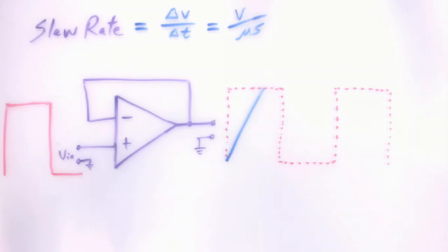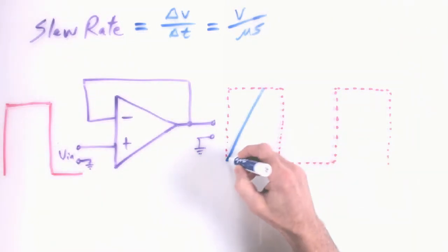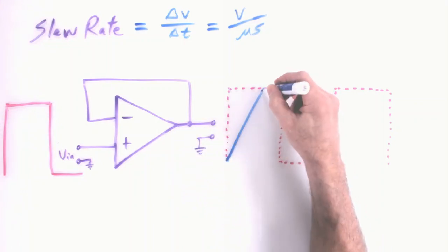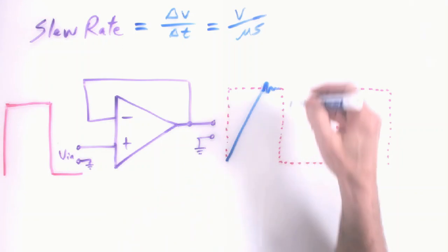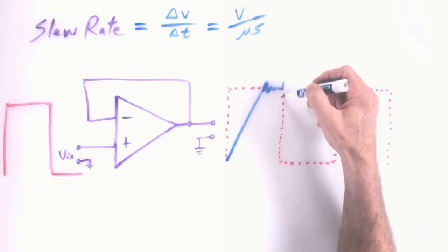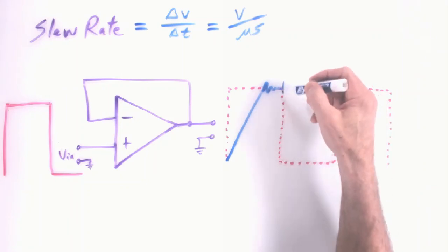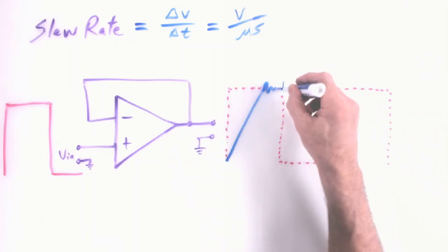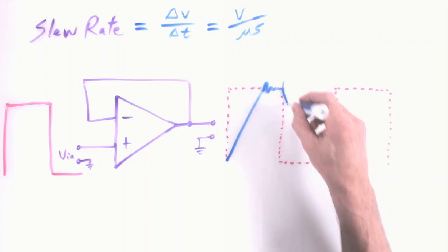Clicked the wrong button. So you'll see things like what's called settling time. It'll go as fast as it can trying to get there, and then it has to slam on the brakes. So there might be a little ringing and settling time. And then when it gets told to go, it gets slammed in the other direction, little magnetic fields collapsing, a little spike, who knows. But yeah, you'll see all these things. Settling time's a big deal too.